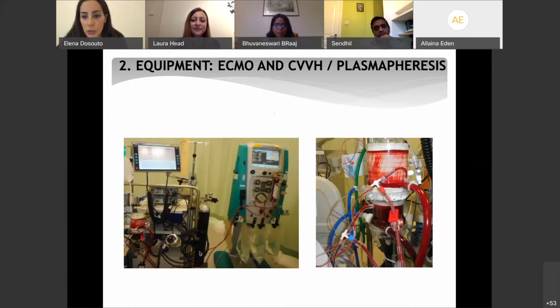We attach the draining port of the filter in here. So in my head, it doesn't make sense because of the different color, like you generally associate blue with drainage and red with return, but the filter is the other way around to make it a bit more confusing. So yes, we drain from here and then re-inject whatever we filter through here, pre-membrane, in case there is any bubble, the oxygenator is going to catch it. And the same applies to plasmapheresis.